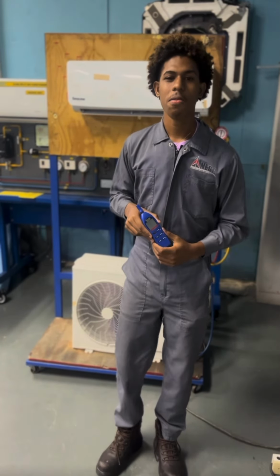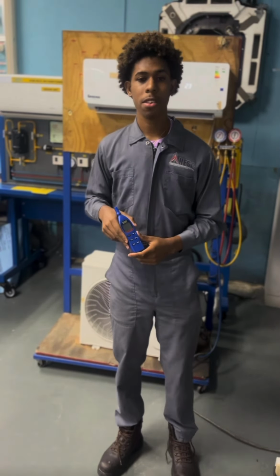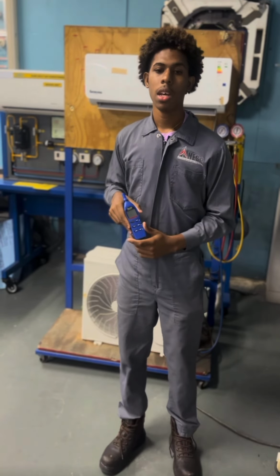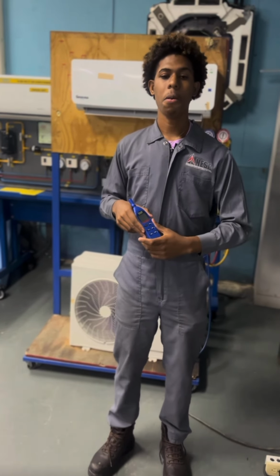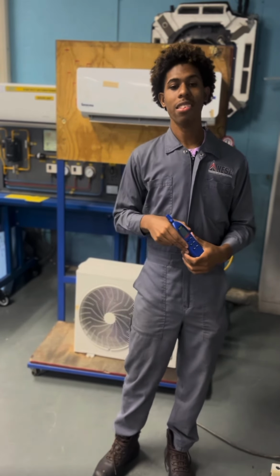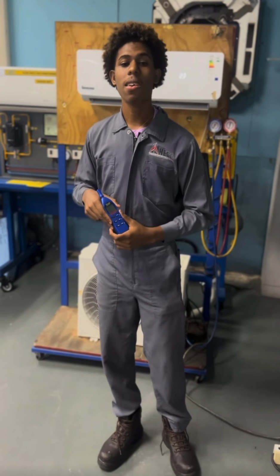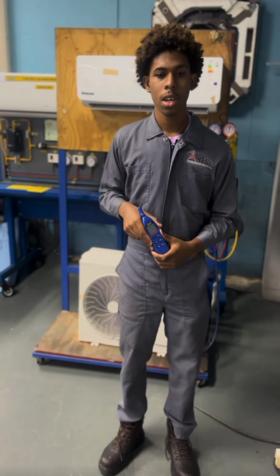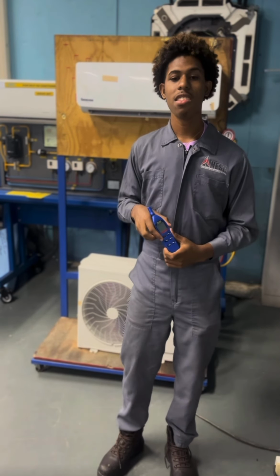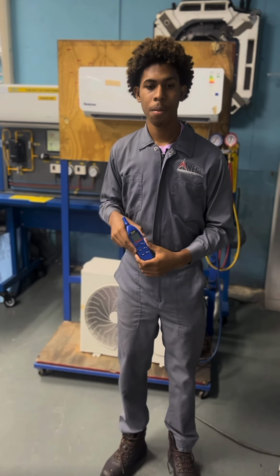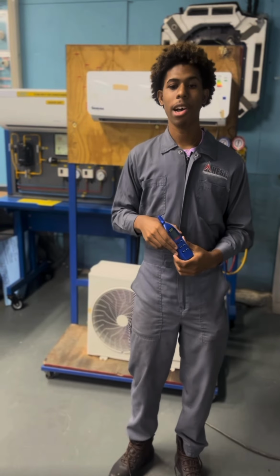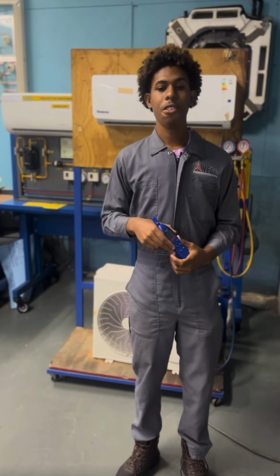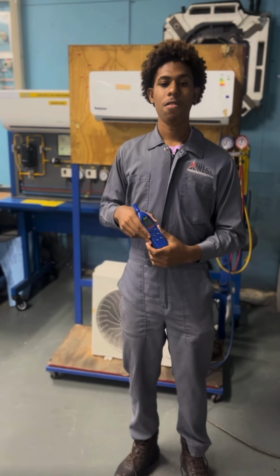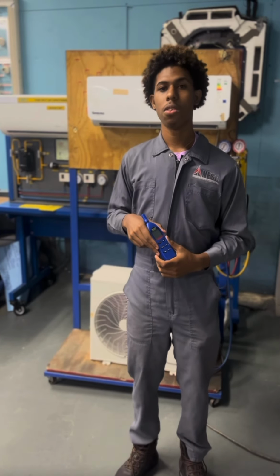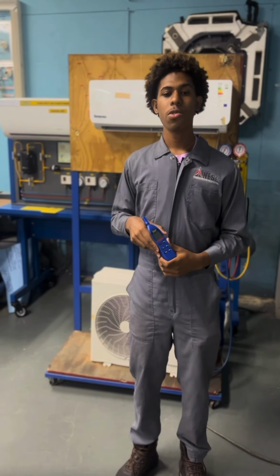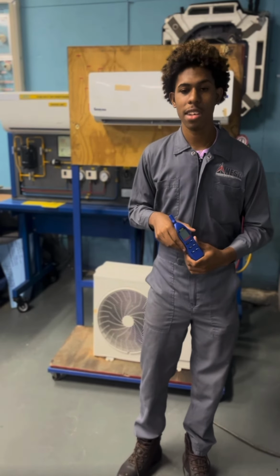The psychrometer is used to measure dry bulb temperature, wet bulb temperature, and relative humidity. These measurements help determine important air properties such as dew point and enthalpy, which are essential for assessing comfort and HVAC system performance. A traditional psychrometer consists of 2 thermometers connected by a swivel. One measures the dry bulb temperature, while the other has a wetted wick covering the bulb. As air passes over the wet bulb, evaporation causes cooling. The difference between the 2 temperatures depends on the humidity level.